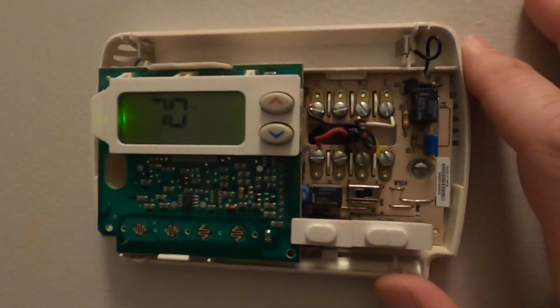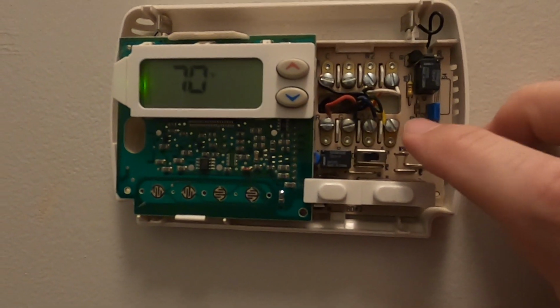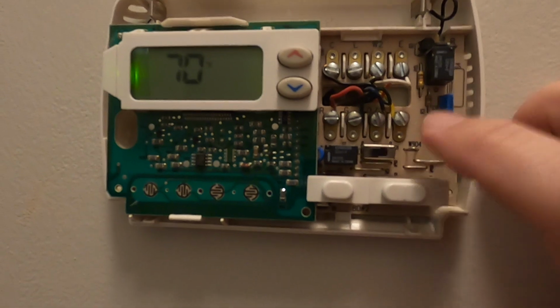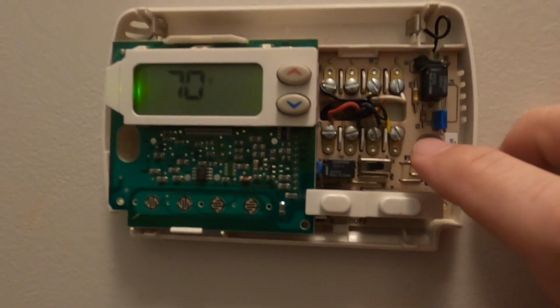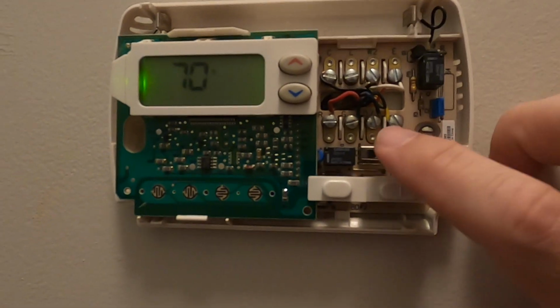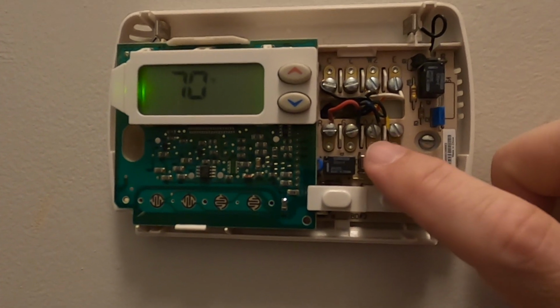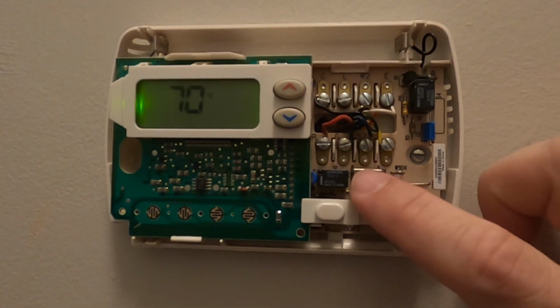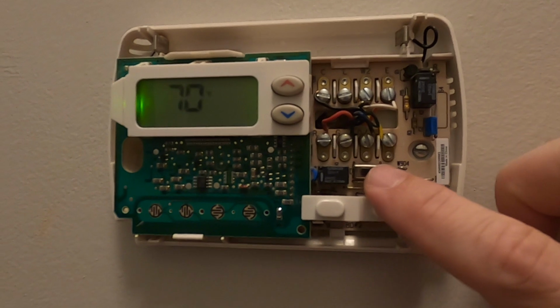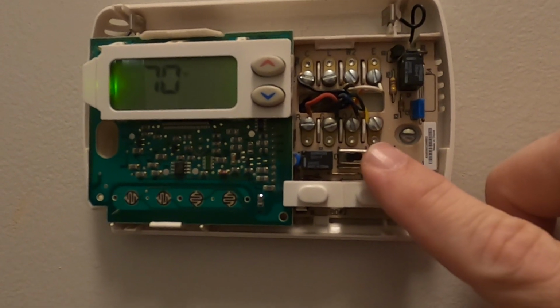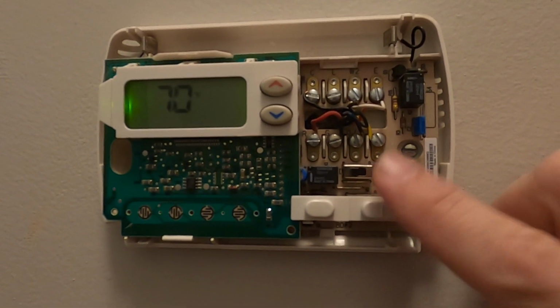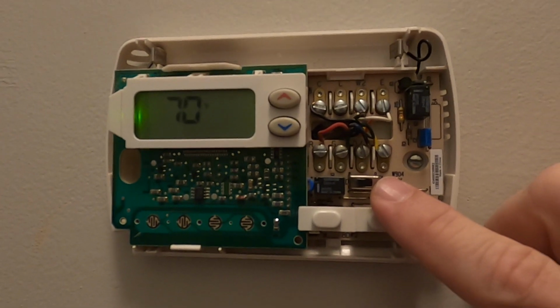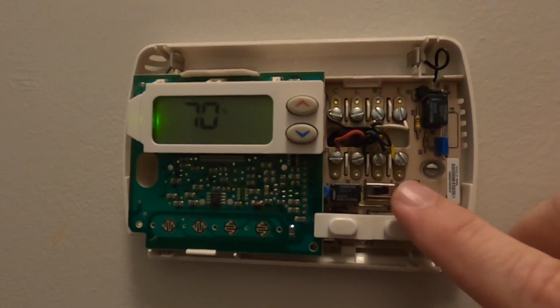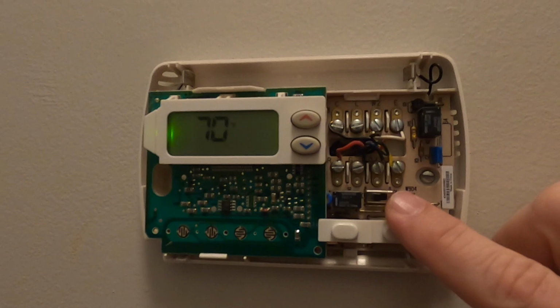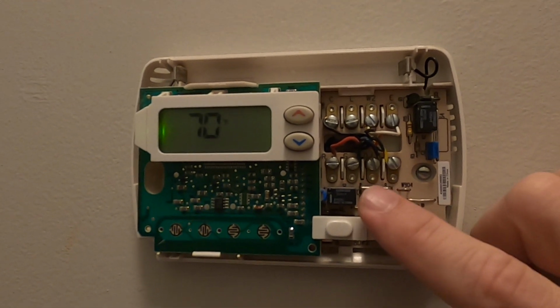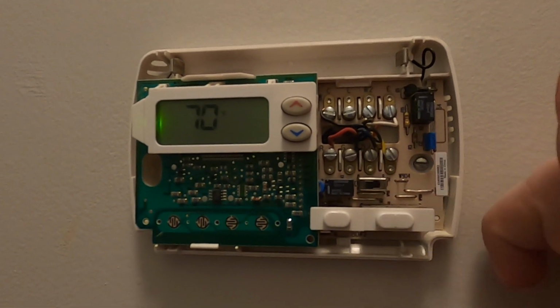All right, one quick correction to what I said. I said that the yellow wire is cool. I misspoke. On a heat pump, the yellow wire tells the compressor to come on, and then the reversing valve tells it whether to be in heat mode or cool mode. So just a quick correction on there. The yellow is going to be on, I should have voltage on that, regardless of whether I'm in heat mode or cool mode, because that tells the compressor to come on, which it has to do in both heat and cool. And then again, the reversing valve tells it whether it is heating or cooling.